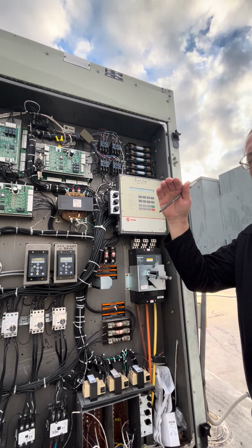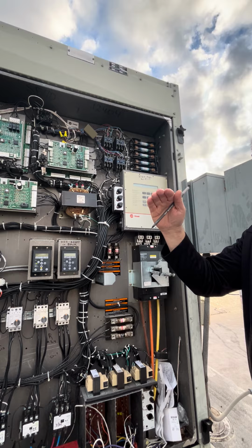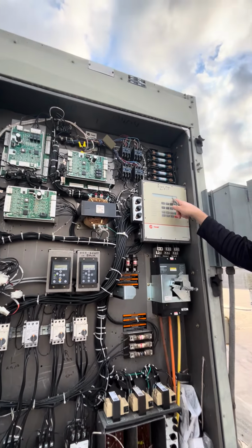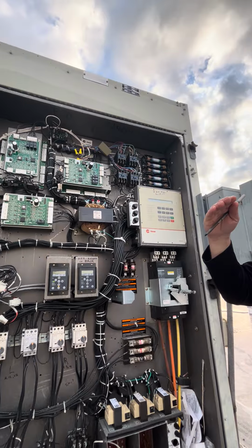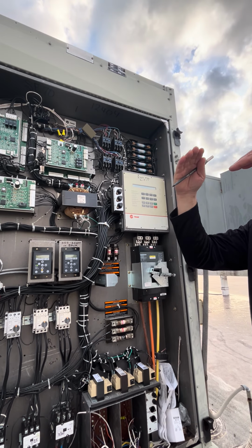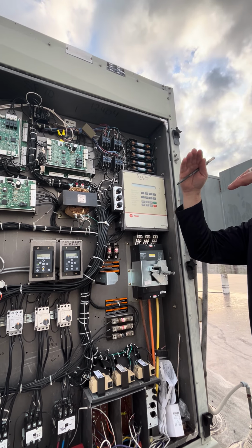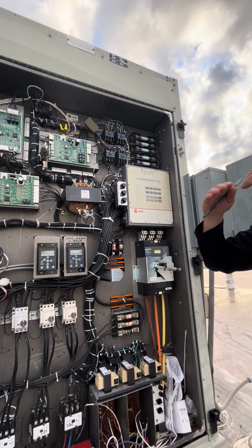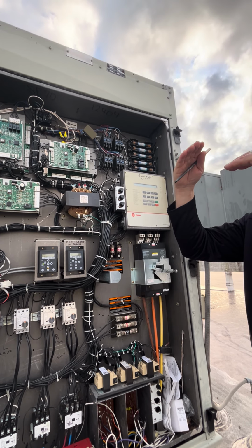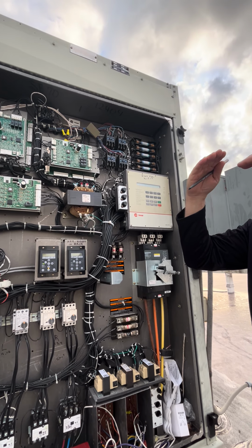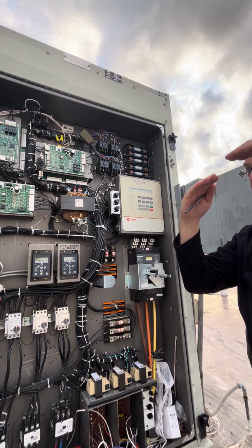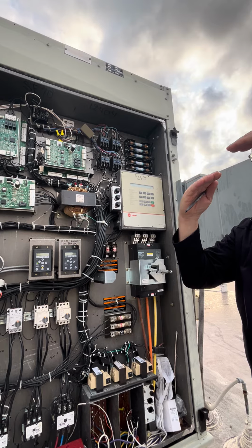Now the temperature downstairs all of a sudden is 73.9, 73.8, 73.7. You're going to see this go from 50 to 51, 52, 53. As the temperature's going down, this is going up. It may get to 60, 62, 63 if this keeps falling. If this levels out, well, then this will hold. If this keeps falling, this goes up. If this starts to increase, then this would come down. So it's just kind of sitting like this. Right.